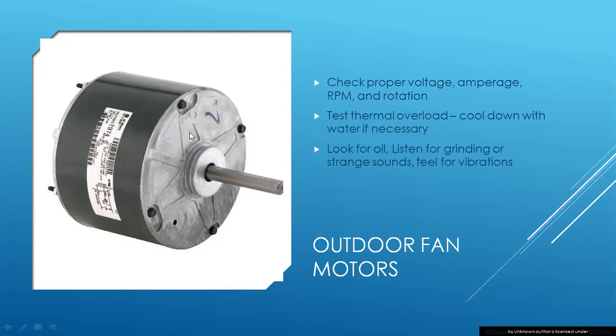One other thing, I got burned one time by this. I had a bad capacitor and my fan motor was basically overheated. And I didn't really know that at the time because I was still young. These motors also, like compressors, have fan overloads in them. So if you're out there on a bad capacitor situation, don't jump right into a fan motor. It may just be overheated. If you can touch the case of the fan motor and it's really, really hot, you can bet that your overload is probably open. And then if you ohm out your wires, you'll find that your common is missing. And if the overload is open, just take a garden hose, spray it down. It'll reset. You'll be back in business.